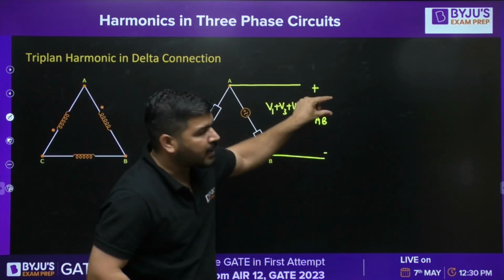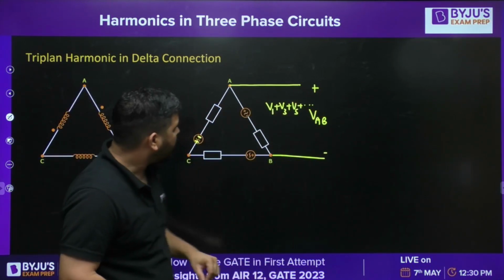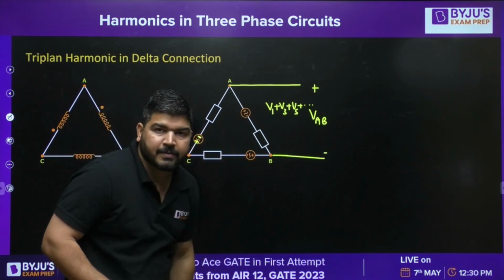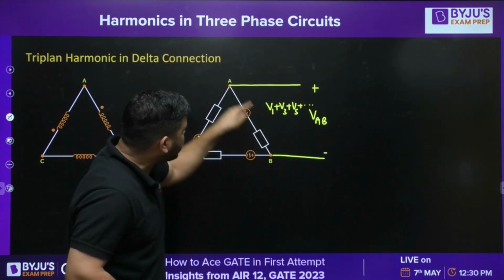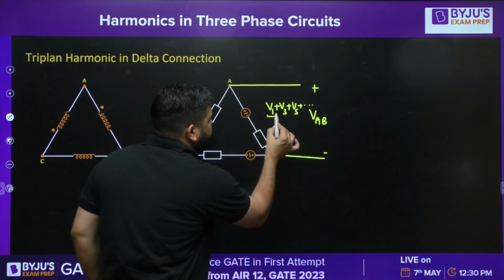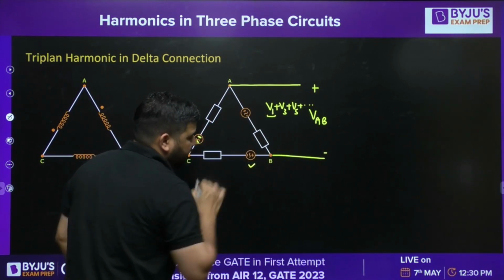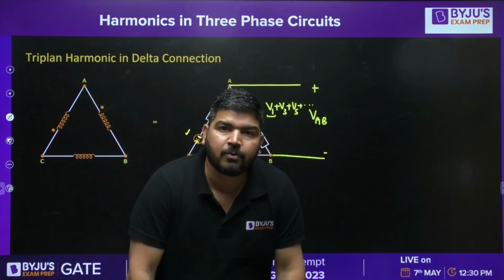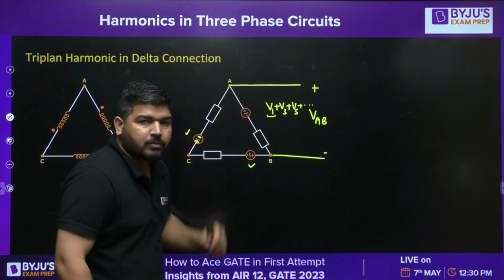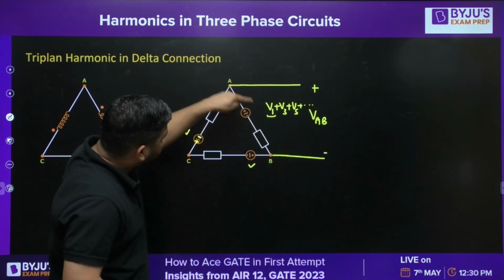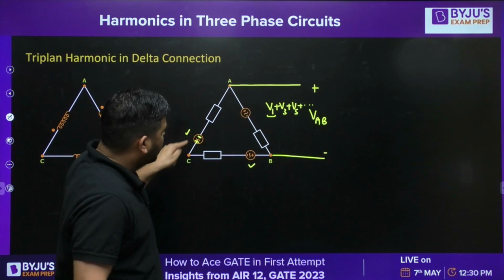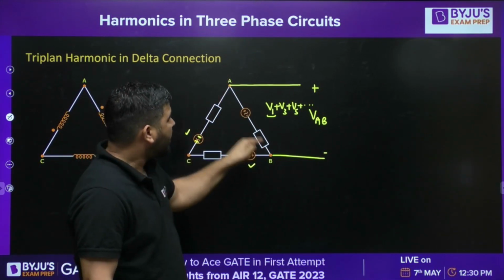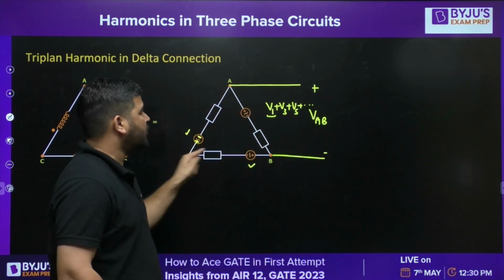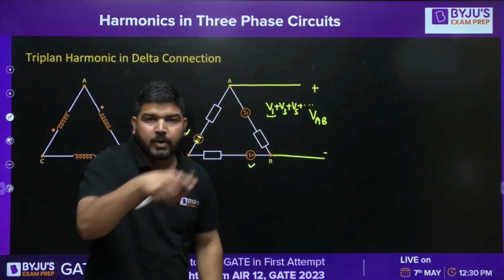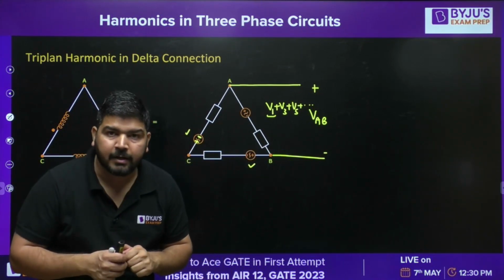In this phase, fundamental, third and fifth are all there. Similarly, in this phase, if you move in a loop and add the fundamental of this phase, this phase, and this phase, they are 120 degrees away from one another, so their sum will be zero. It means there is zero total voltage of the fundamental component. There is no fundamental component in this loop, so there will be no circulating current due to the fundamental component.